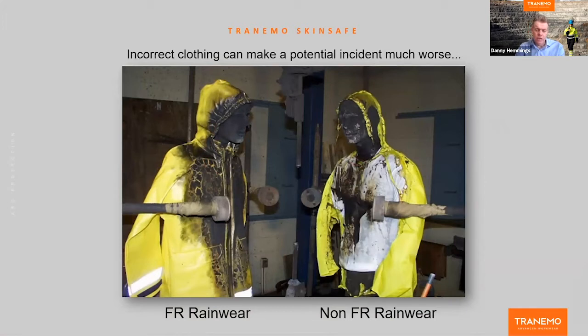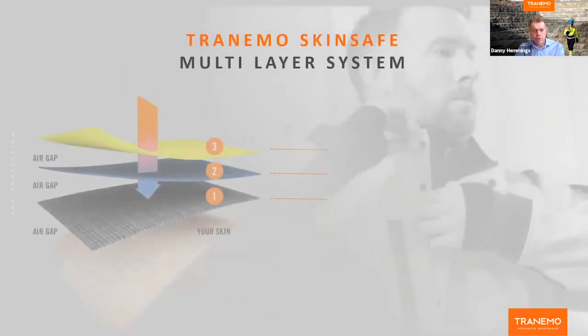We then go the other way and look at rainwear. You'll see on the left side, that's a post-arc test of a flame retardant arc jacket, rainwear jacket. So you can see charring from the explosion, but it stayed intact, clearly hasn't burnt. And you compare that to the image on the right, which is a standard high visibility rain jacket, no FR protection, no arc protection. And you can see most of the front of that garment is completely obliterated in the arc flash. And as that's obliterated, it will have turned into molten debris. And you can see there on the front of the mannequin that debris has stuck and burnt onto the base layer underneath. So vitally important that layers are complementary.